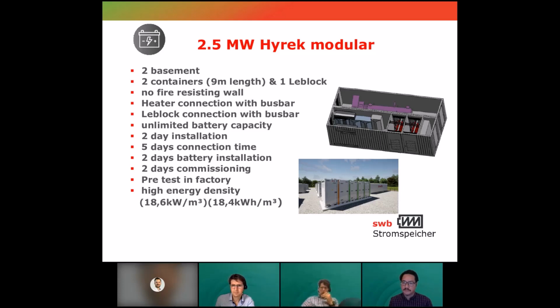inside the second container. But we go away from the 40 feet container to a 9 meter length container, and one Le Bloc system separate. With this, we only have to do the connections with the bus bar to the Le Bloc, and the connections to the mid voltage side, and can decrease the installation time to 2 days. The connection time scales down to 5 days. We delete the battery installation time and the high amount of manpower on site. We can pre-test this in the factory and have a high energy density with 18.6 kW per cubic meter.